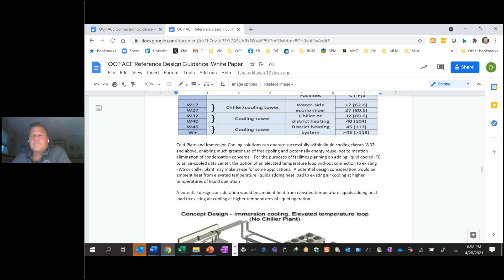AC, I think you're doing both elevated temperature and a facility water solution, a chill water solution, aren't you? Yeah, correct, mine's a dual loop system. The first one uses the chiller plant, traditional one, using a high water temperature, roughly about 17 degrees. The other uses ambient, using dry coolers or cooling towers - that one can vary quite widely, as low as 2 degrees, no, 4 degrees. So it's pretty wide.